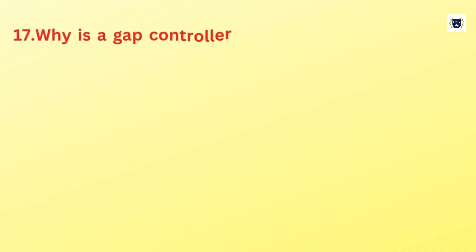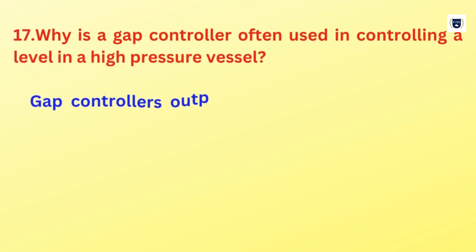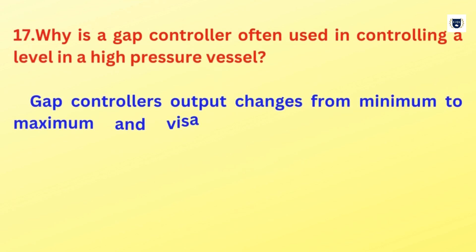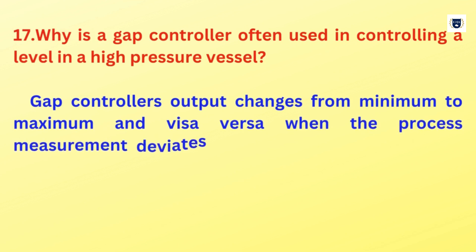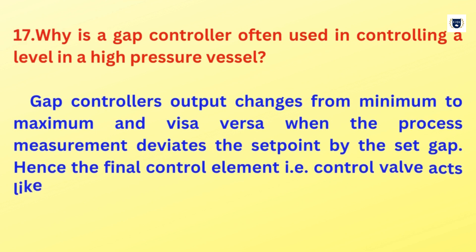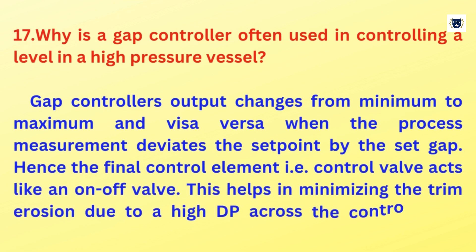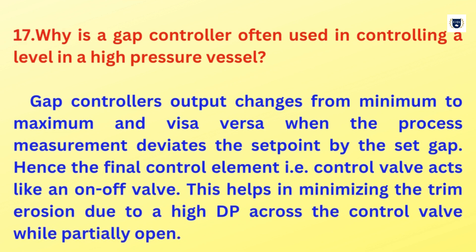Why is a gap controller often used in controlling a level in a high-pressure vessel? A gap controller's output changes from minimum to maximum and vice versa when the process measurement deviates from the set point by the set gap. Hence the final control element, i.e., the control valve, acts like an on-off valve. This helps in minimizing the trim erosion due to high differential pressure across the control valve while partially open.